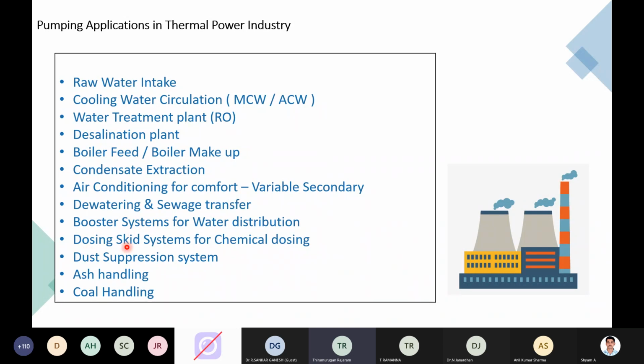The one which I mentioned, the dosing skid system for chemical dosing. Here we talk about energy optimization in centrifugal pumps, whereas in your dosing pump, chemical optimization comes into the picture. Because when you talk about the tariff for energy, maybe 7 rupees in India, whereas if you talk about the chemical cost, that will vary in thousands. Even a 1 liter or a 200 liter can, whatever the cost, is very high, and we are not going to leave that either. Until you do precise dosing, you will have a lot of avenues to save it.